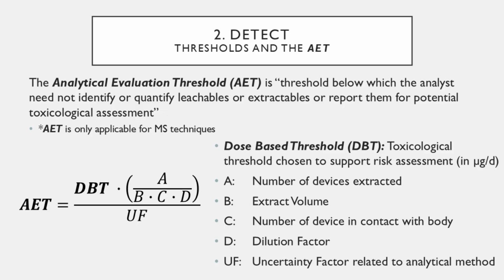The extraction volume, that's going to dilute your sensitivity. So, just like in the example I gave previously, if you extract your medical device in a 10-gallon tank, then maybe that's appropriate. Maybe for whatever reason, that's what you need to do. But that's going to dilute your AET and require much higher sensitivity. Again, because it's very feasible that if I have some toxic compound, but I put it in a 10-gallon extraction pool, I'm not going to be able to see it. Why? Because it's not feasible for me to have that level of sensitivity. If I truly want to put it in something of that high amount of solvent, I need to then justify that I have the sensitivity to overcome that dilution factor.